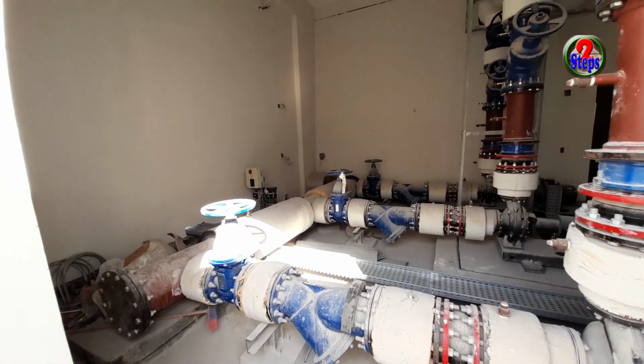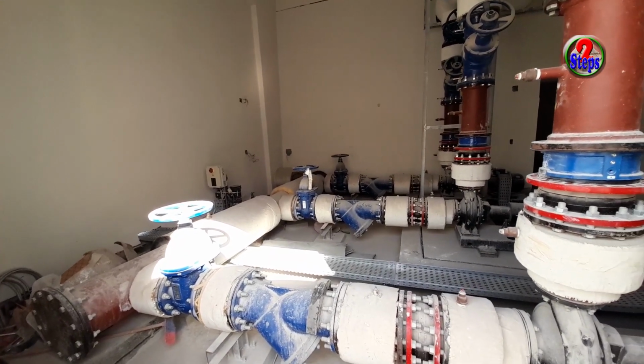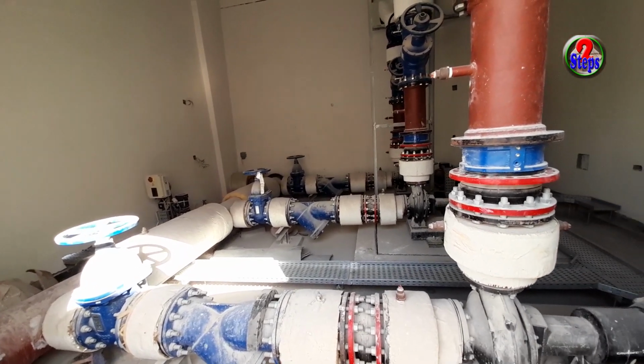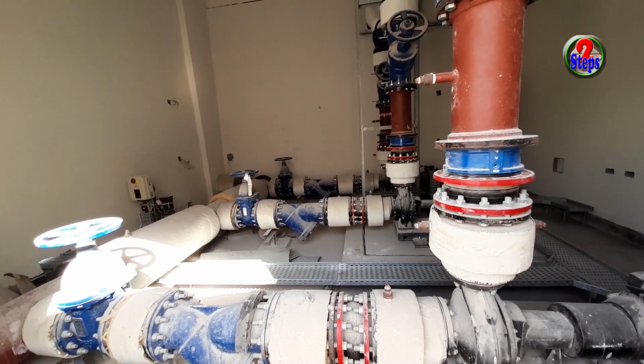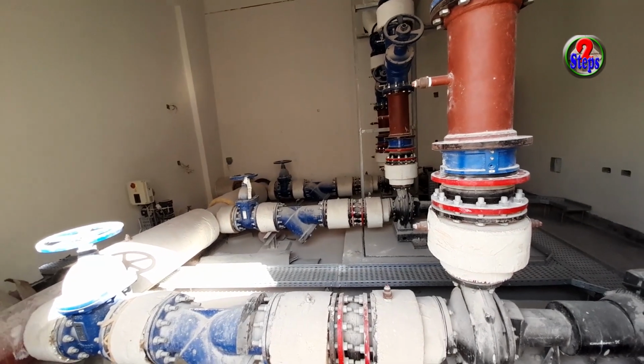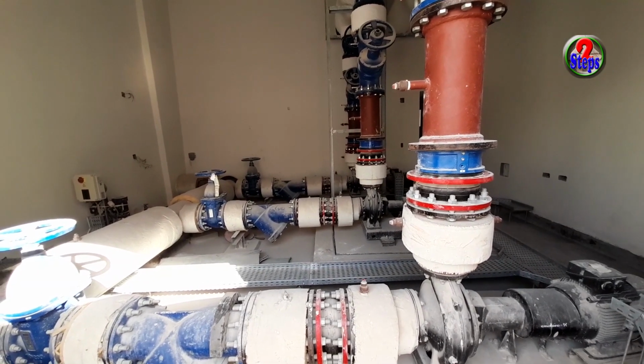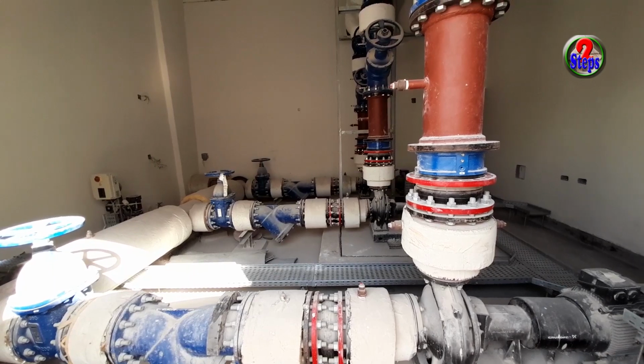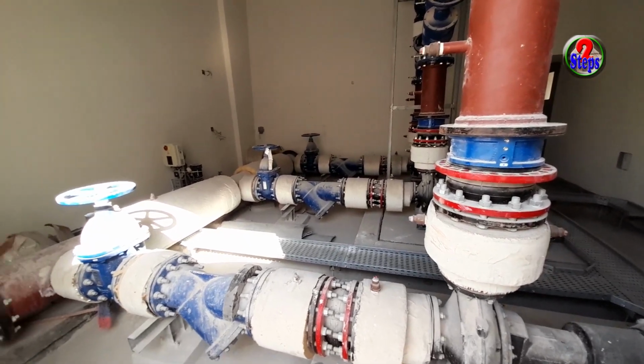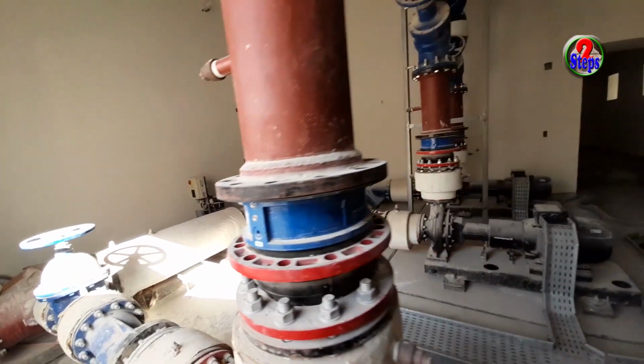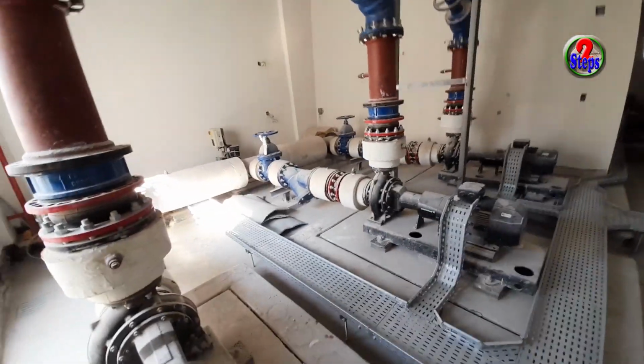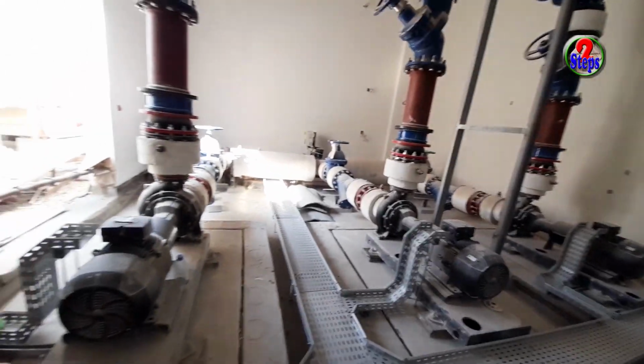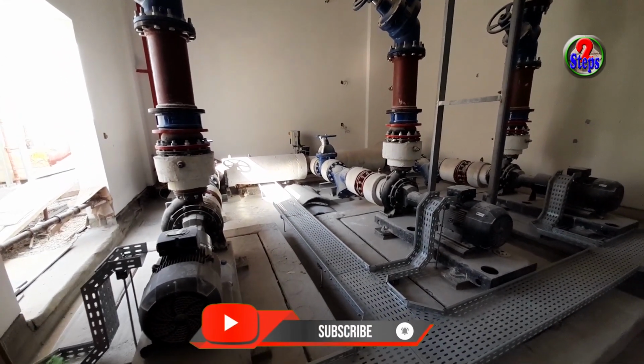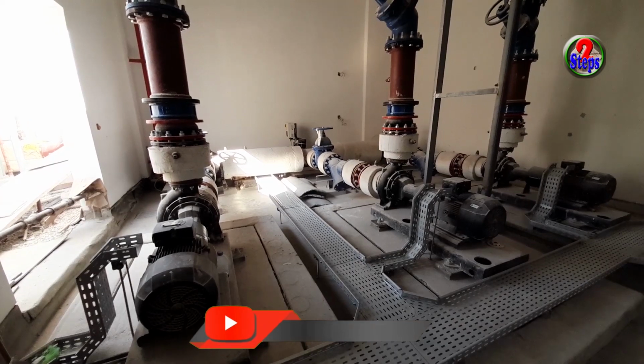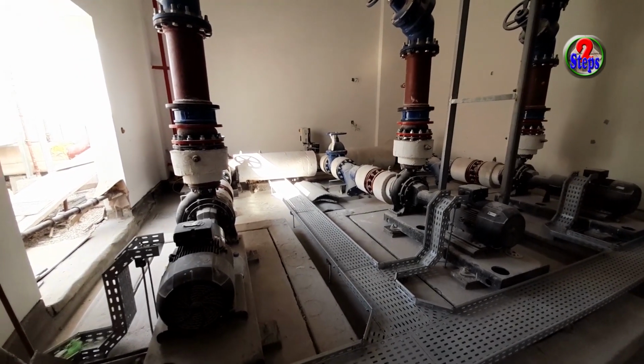Hi viewers, now I am in a pump room. Every chilled water system has two pump sections: one is the primary pump section and the other is the secondary pump section. This one is the primary pump section. This system has three pumps, matching the three chilled water chiller machines. Here also, two are on duty and one is on standby.